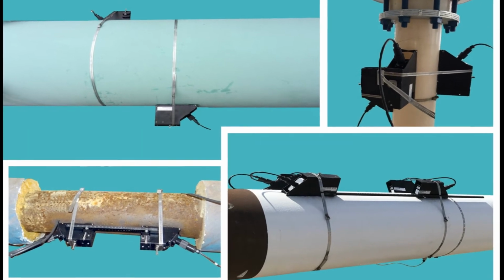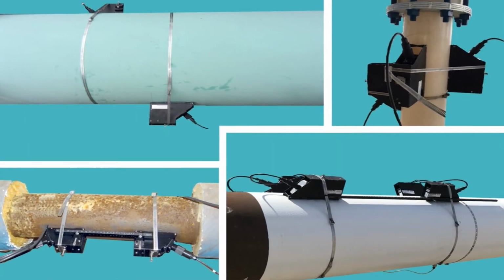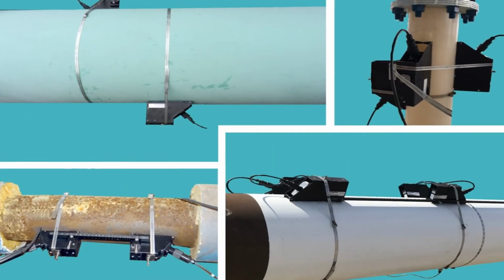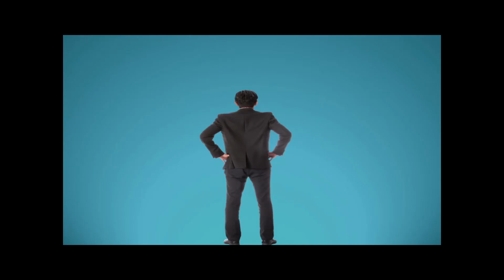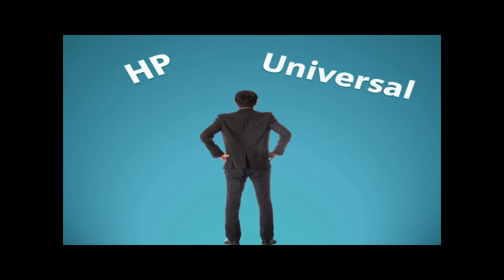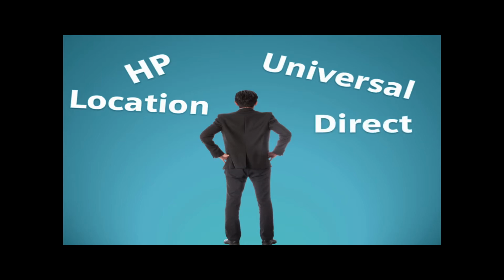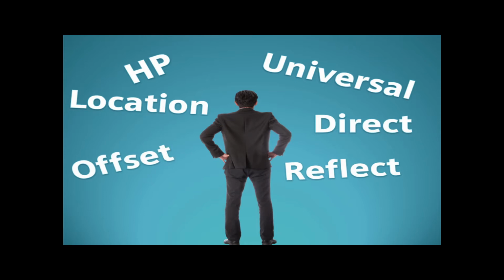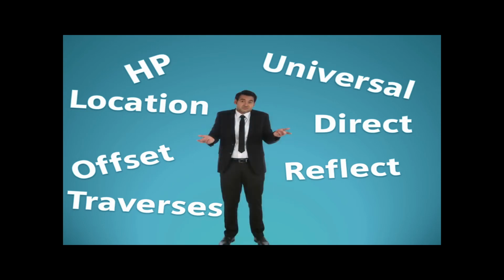When it comes to installing your FS230 or FS220 flow meter, you're faced with a number of decisions regarding how to mount your flow sensors. Do I have high precision or universal sensors? Where should I mount the sensors? Should I mount in direct or reflect? What spacing offset should I use? And what's a traverse? Confused?